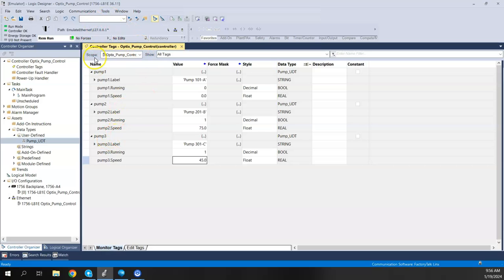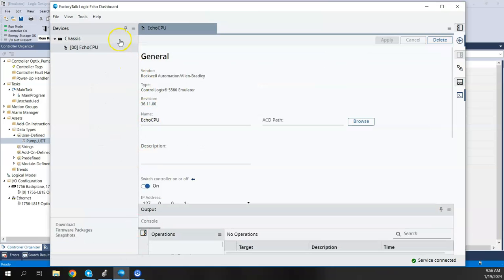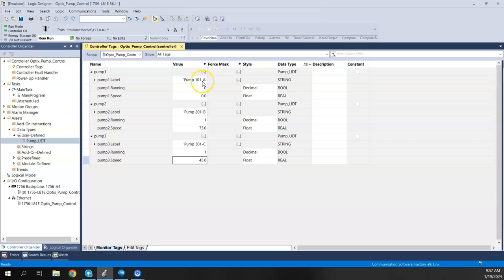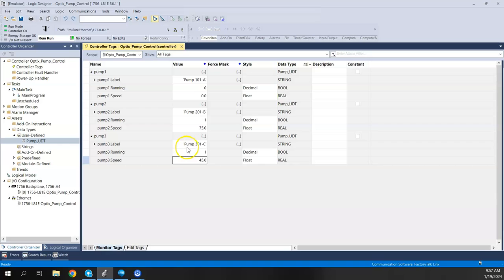Now, this is Studio 5000 and I am connected to my Logix Echo emulator. So this is actually a running controller right now. You can see that I am connected and I am running. And I went ahead and put some values in for label running and speed for each one of the pumps. So Pump 1, I gave it a label of Pump 101A. Right now it's off and zero speed. Pump 2, I called it Pump 201-B. It's running a speed of 75. And Pump 3 is Pump 301C, running the speed of 45. So I can change these values on the fly here once we go into the emulator and see how it works in Optix.